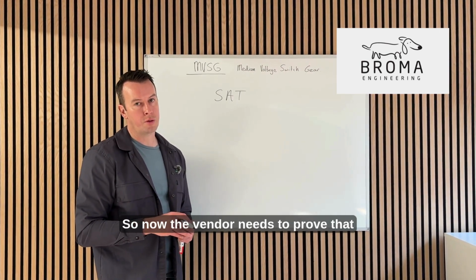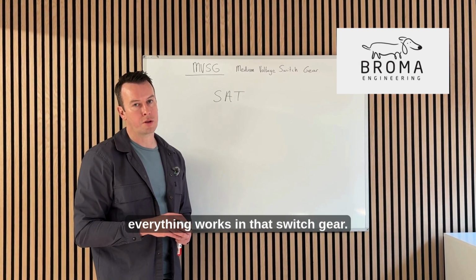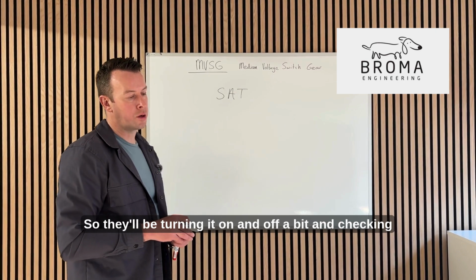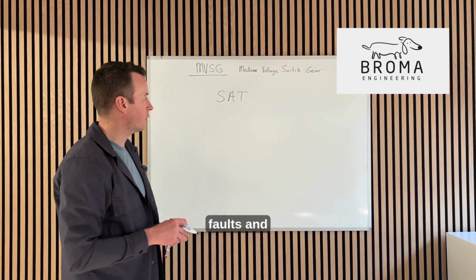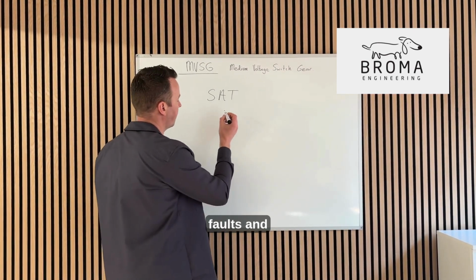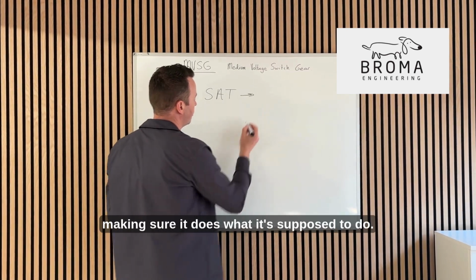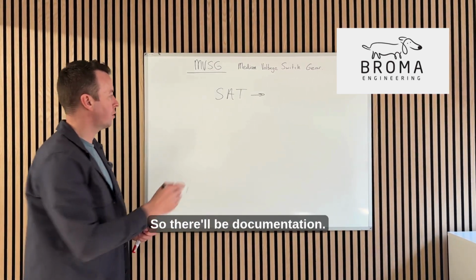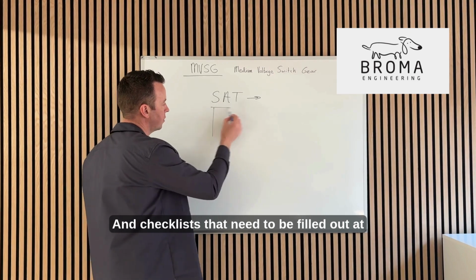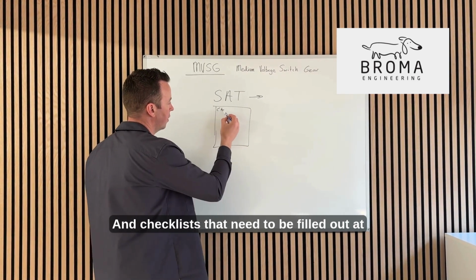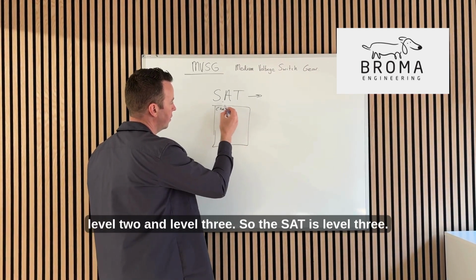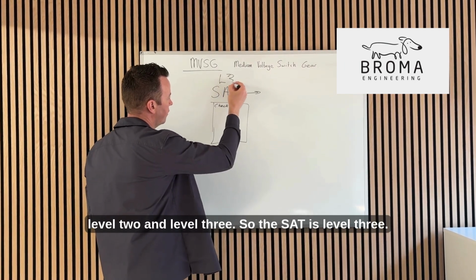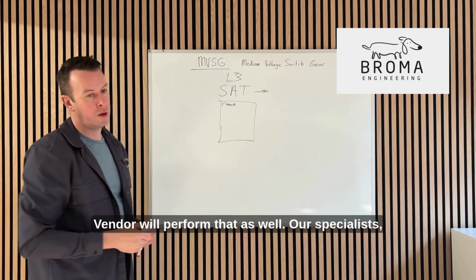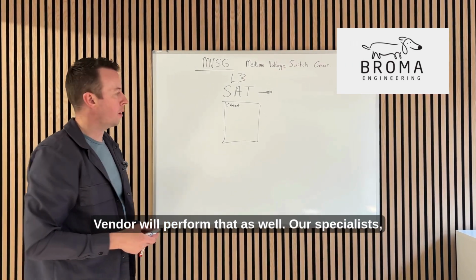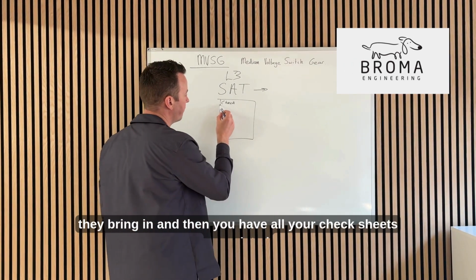Now the vendor needs to prove that everything works in that switchgear, so they'll be turning it on and off a bit and checking faults, making sure it does what it's supposed to do. There'll be documentation and checklists that need to be filled out at level 2 and level 3. The SAT is level 3—the vendor will perform that, or a specialist they bring in.